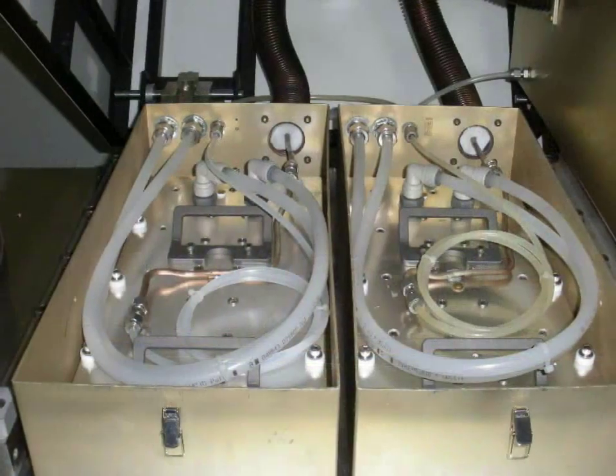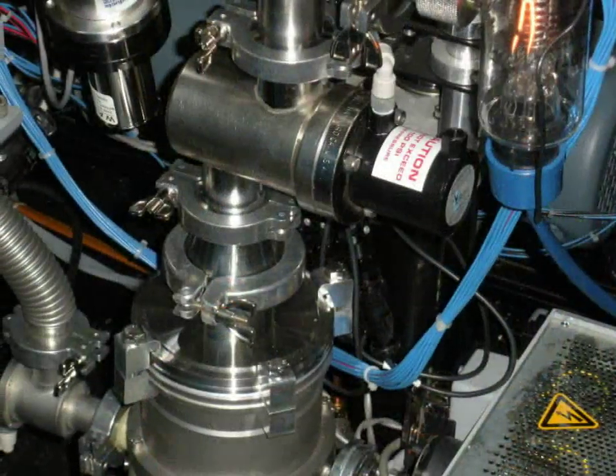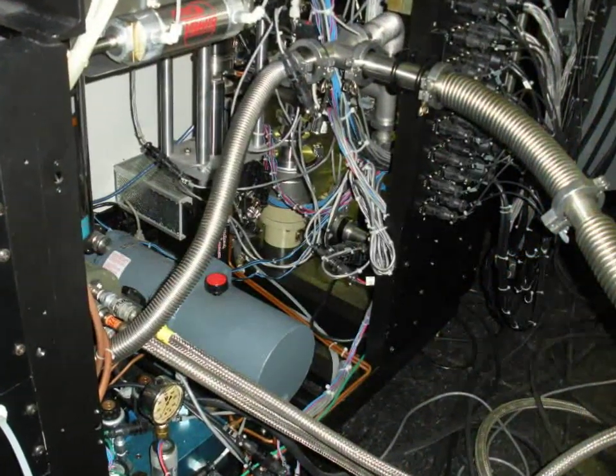The 90X T-Series comes standard with a high-vac pumping load lock due to the use of a Pfeiffer Balzers Turbo Molecular Pump and Controller. This pump has been successfully used for many years on the much larger Perkin Elmer model 4450's load lock chamber.